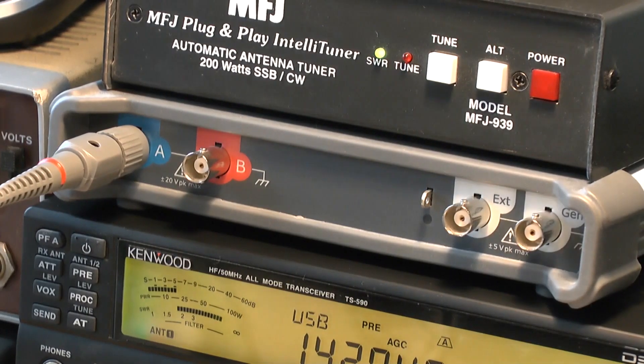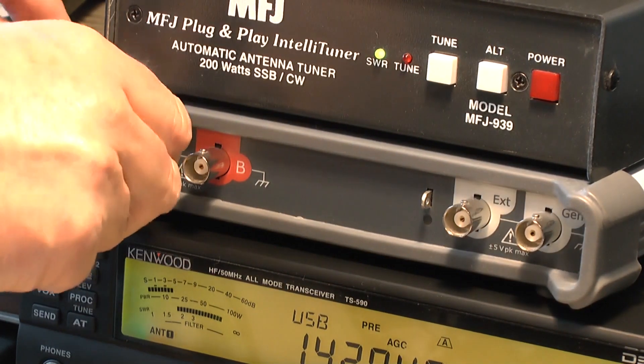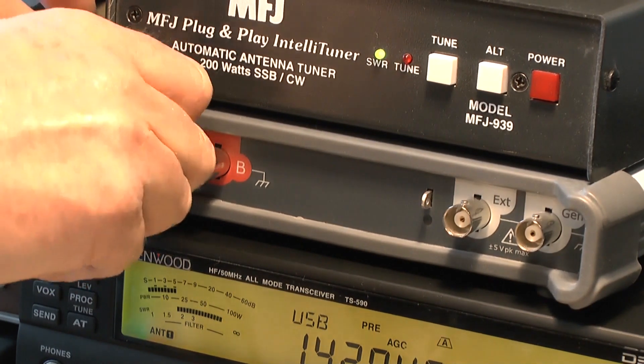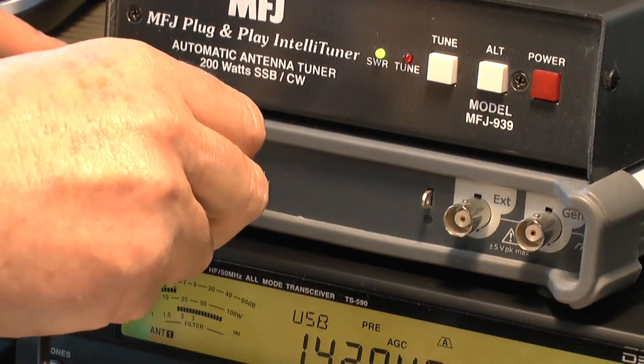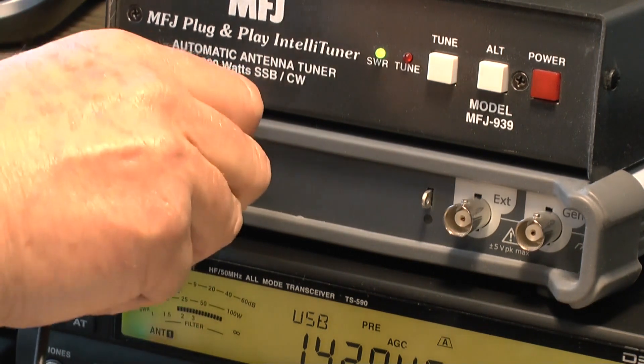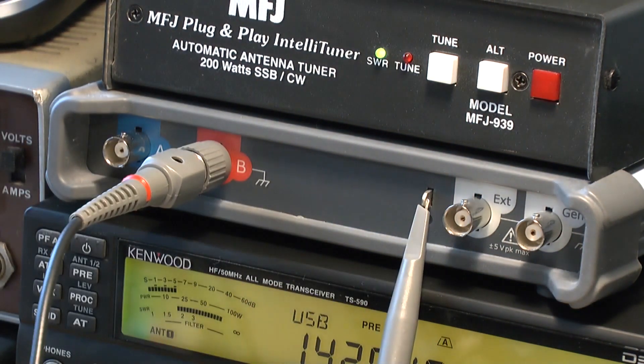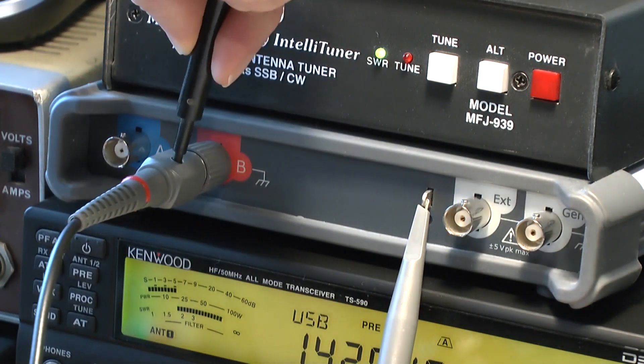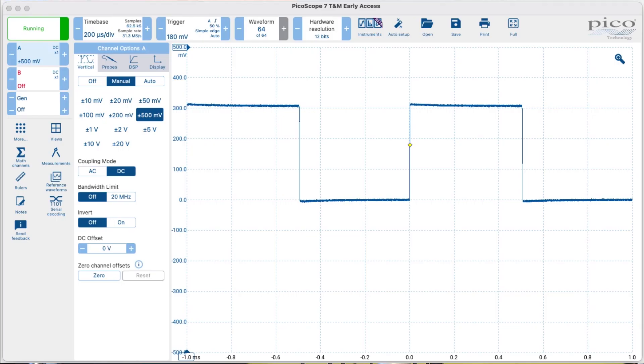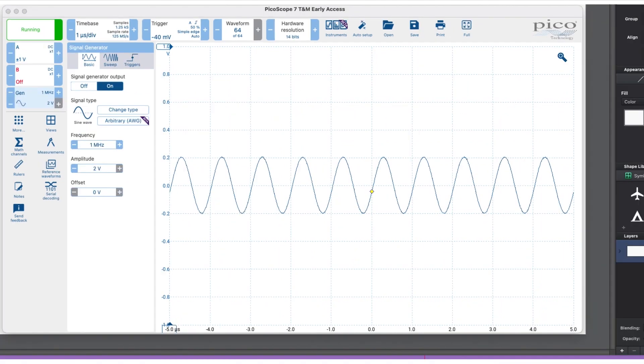It's worth remembering that the probe compensation needs to be readjusted if the probe is used on a different input, even on the same scope. This is because the values of capacitance on different inputs will vary slightly and therefore a new adjustment is needed each time. In fact, it's worth getting into the habit of compensating a probe each time it's used because it may have been used on a different input or a different scope.